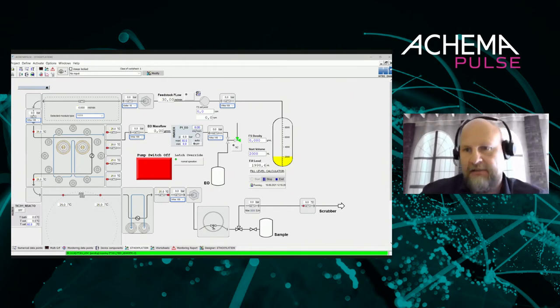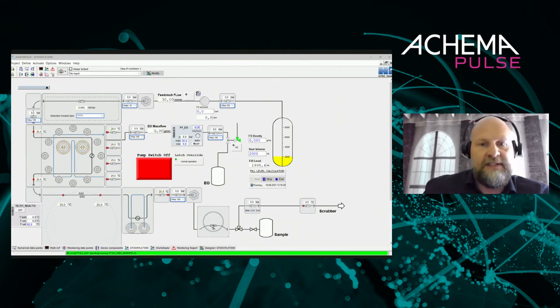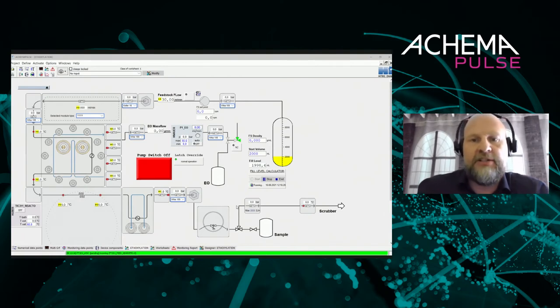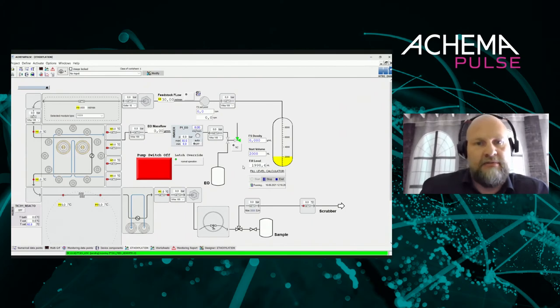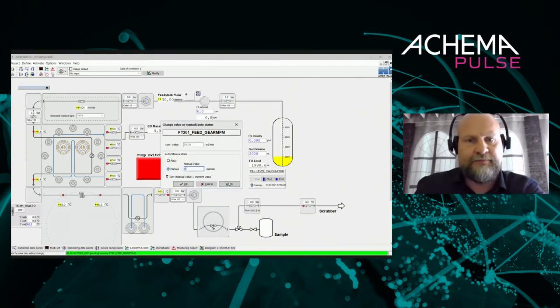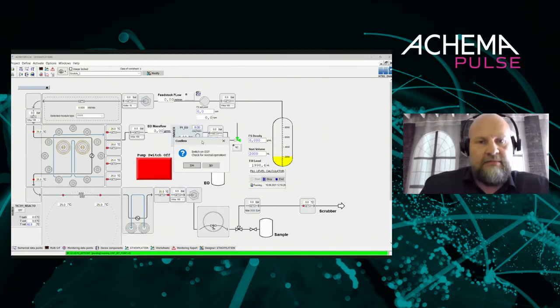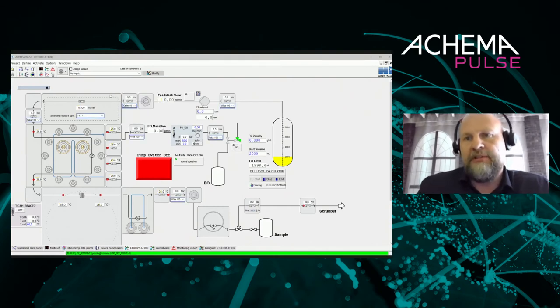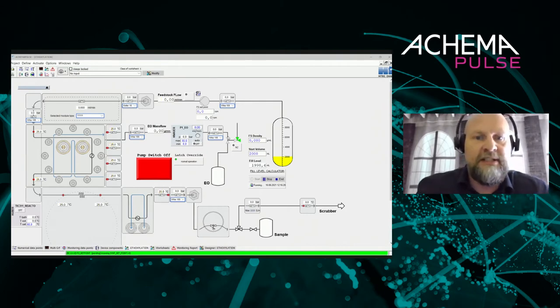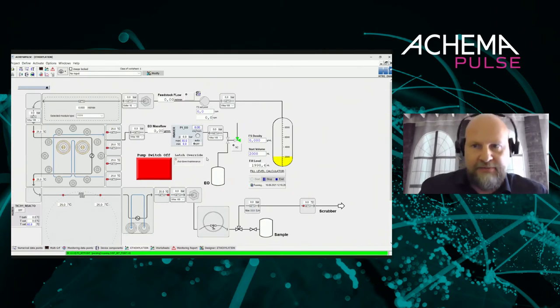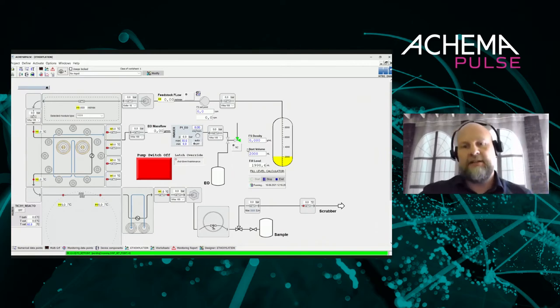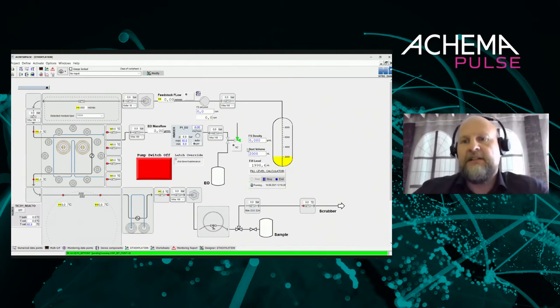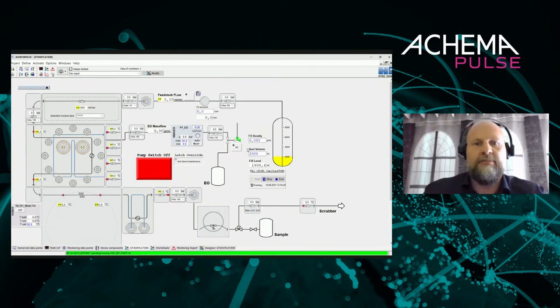Most of the background programs are designed to prevent unreacted ethylene oxide from passing through the reactor. For instance, if the ethylene oxide feed is started but there is no flow on the feedstock line, a warning is immediately generated — because there needs to be something to react with the ethylene oxide. While an override warning is active, you cannot switch on the ethylene oxide. This demonstrates how a very complex automation can be pieced together in a relatively straightforward way.